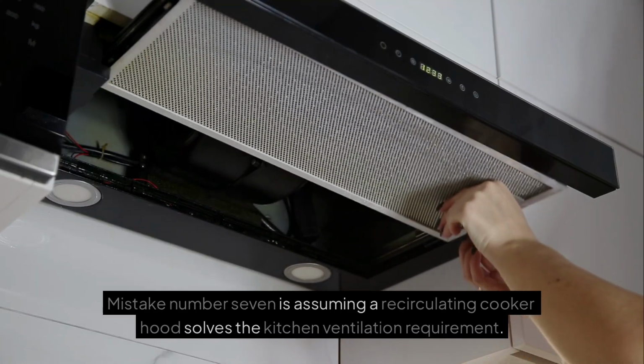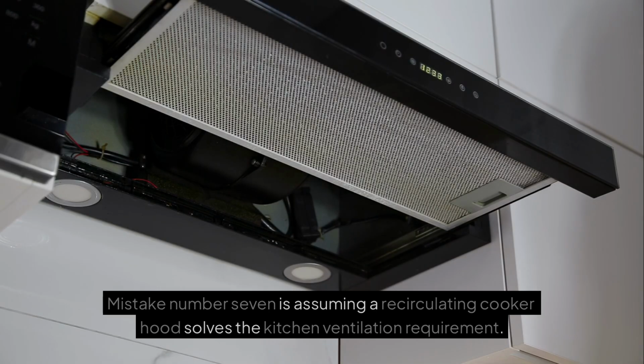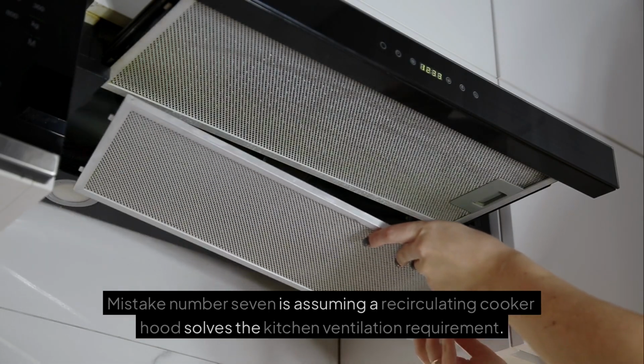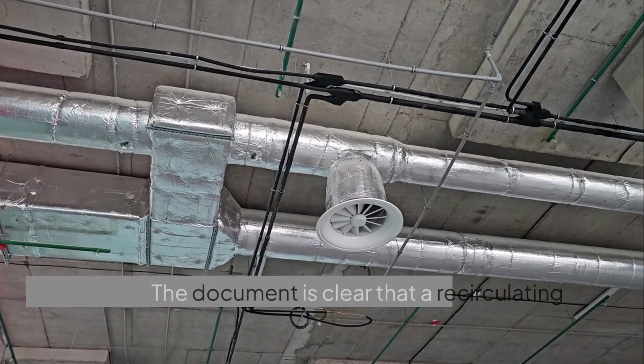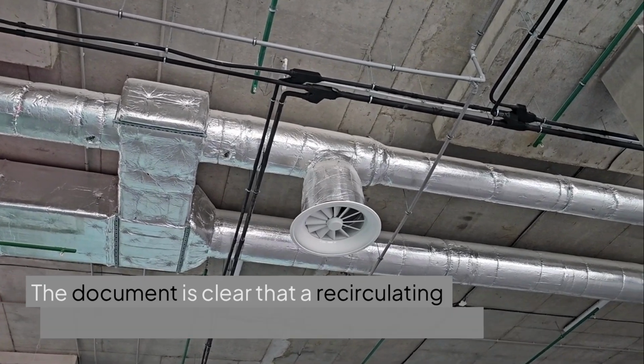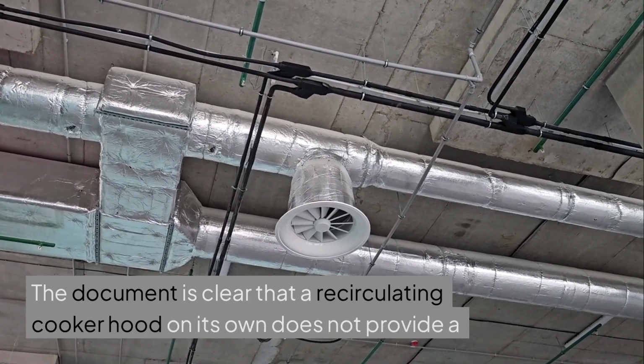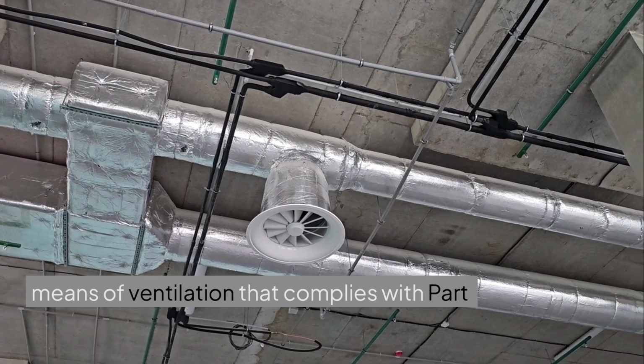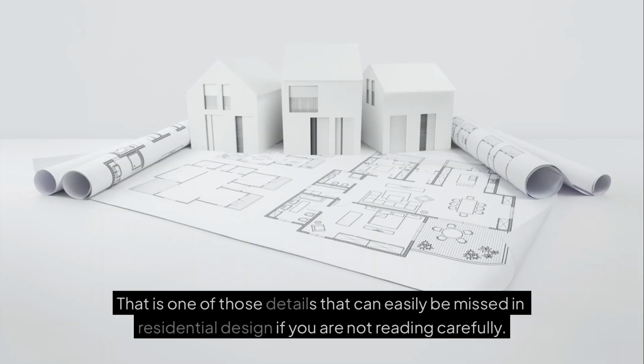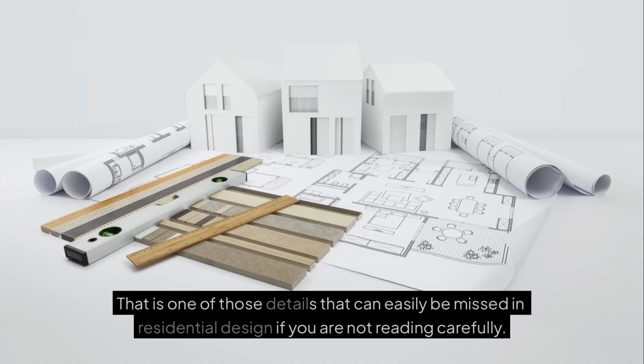Mistake number 7 is assuming a recirculating cooker hood solves the kitchen ventilation requirement. It doesn't. The document is clear that a recirculating cooker hood on its own does not provide a means of ventilation that complies with Part F. That is one of those details that can easily be missed in residential design if you are not reading carefully.